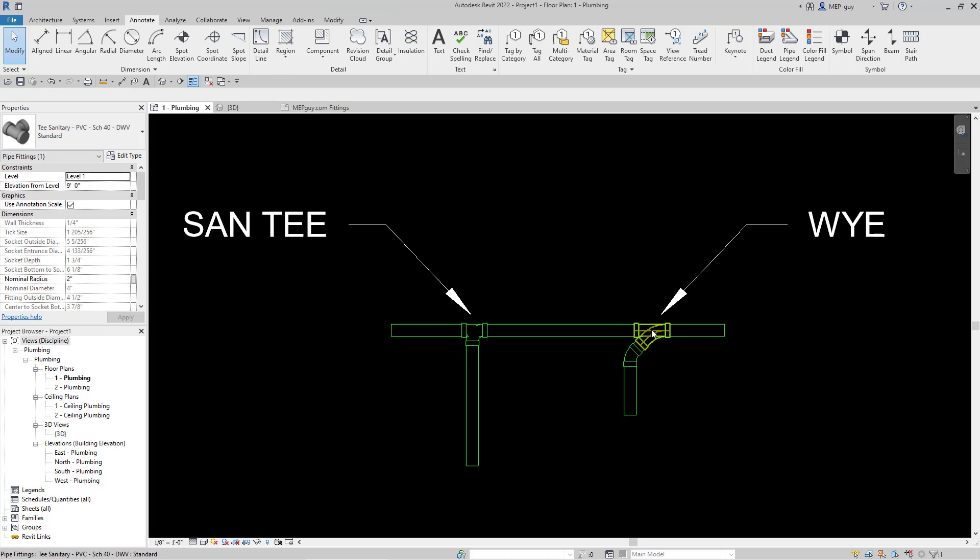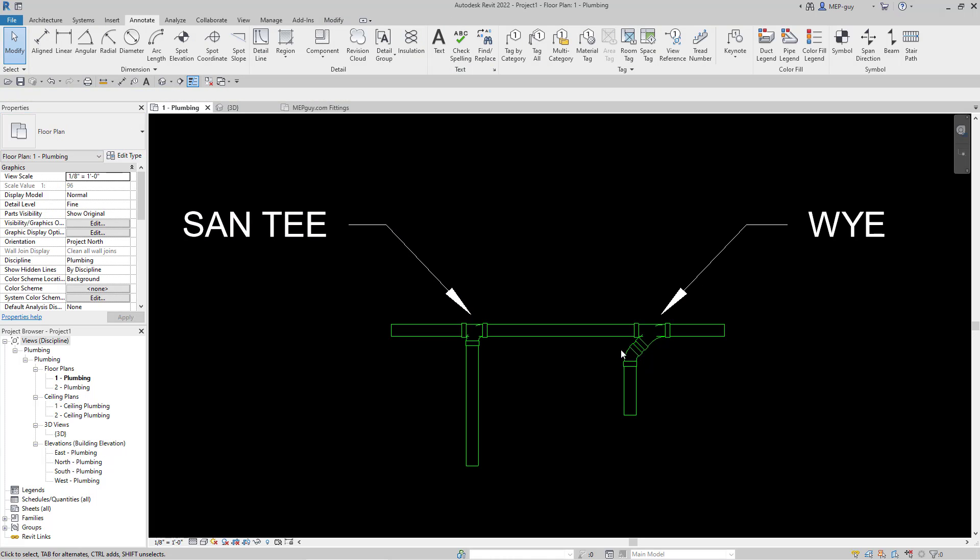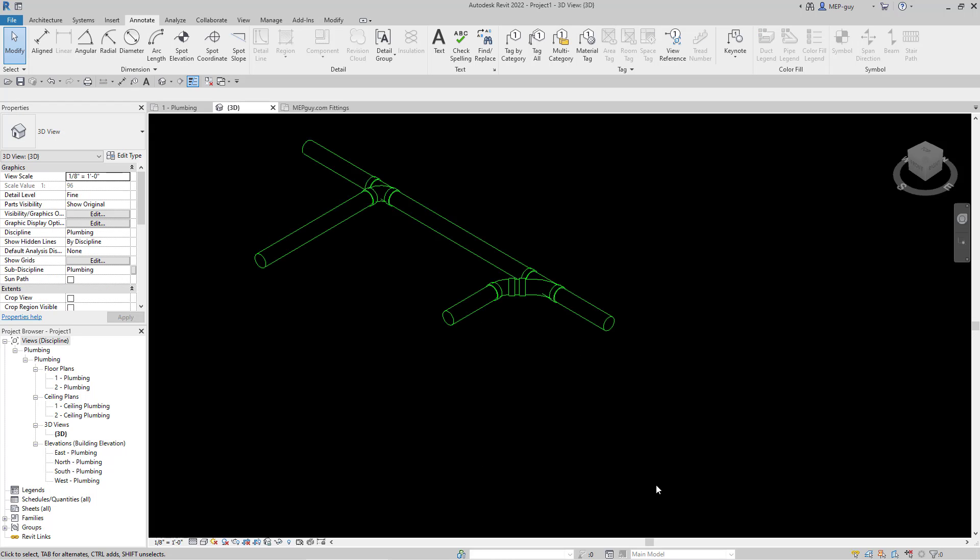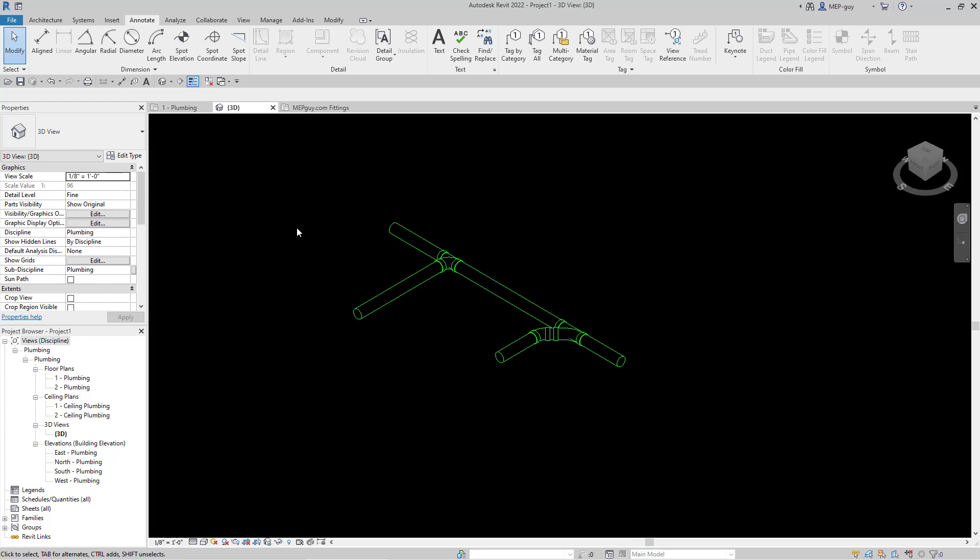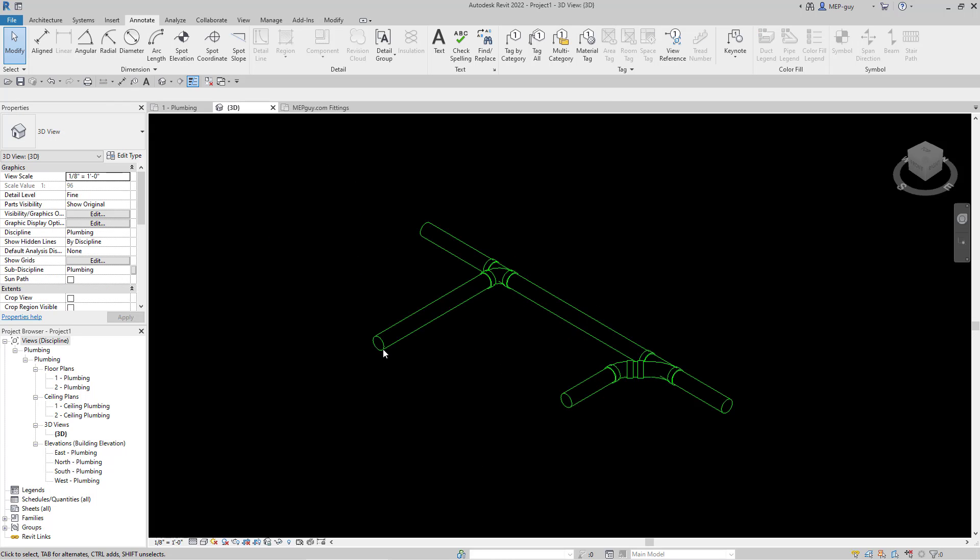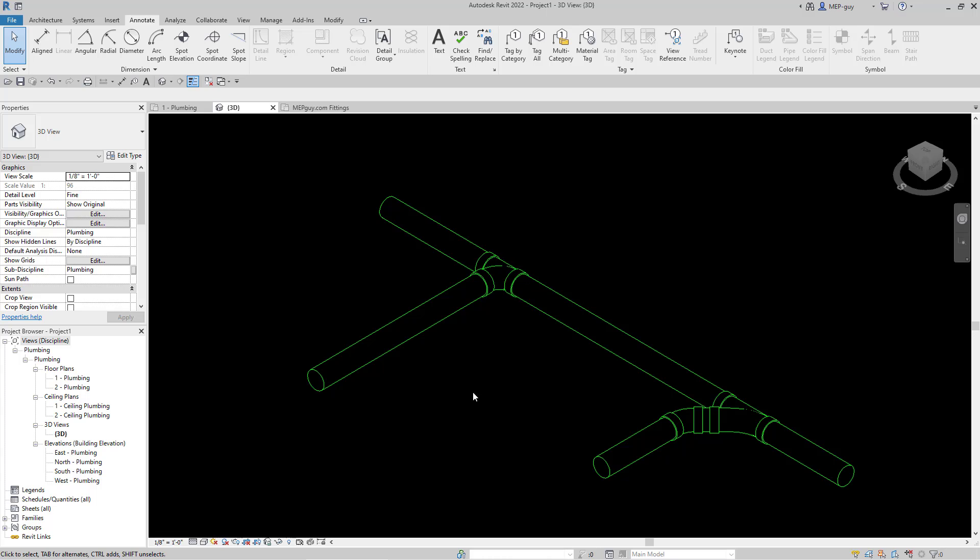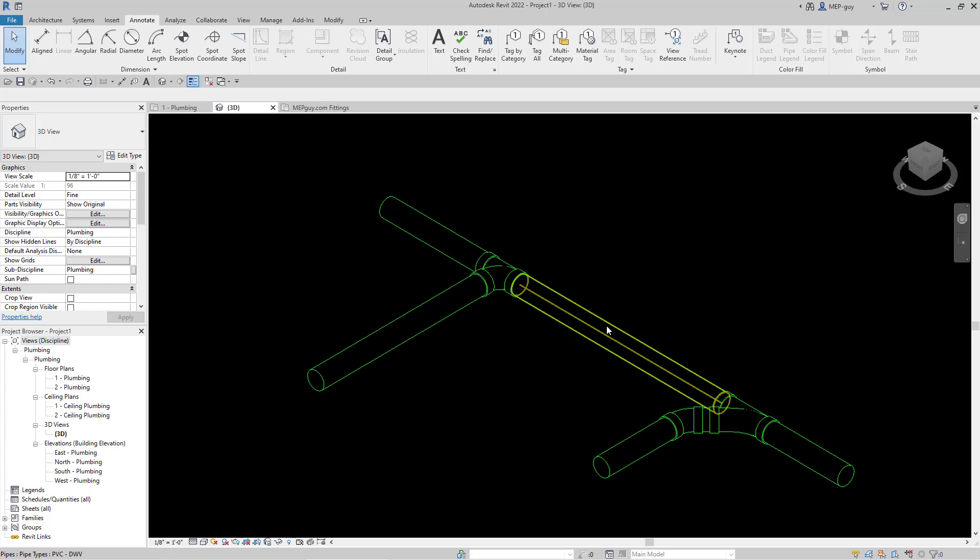Now the difference is that this little fitting is able to go at different angles. So when we're actually drawing plumbing per the international plumbing code, we actually cannot do this if we're working with horizontal drainage piping. And when I mean horizontal drainage piping, I mean that piping that is going horizontally parallel to the floor. And the reason for that is they want nice smooth transitions when we're dealing with sanitary piping.